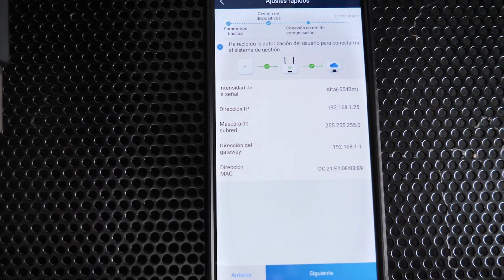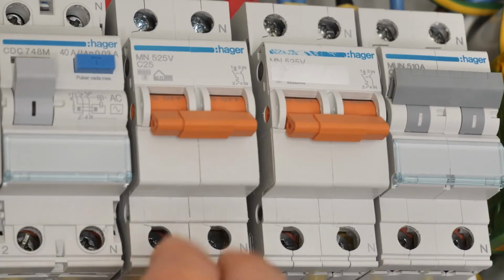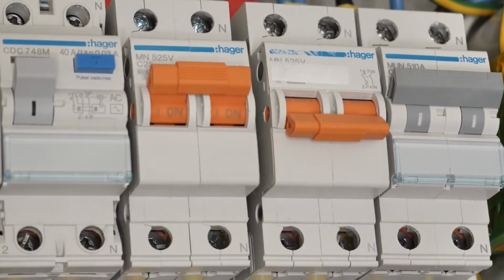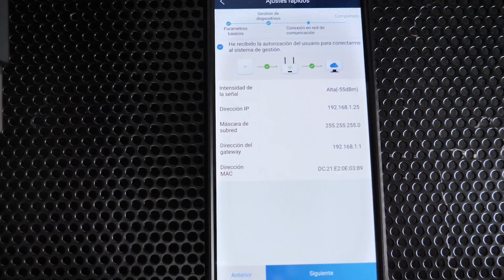In this case we could put the inverter into operation, specifically the alternating current part, since the inverter has already been configured. We would simply have to raise the alternating current protections so that the inverter receives power from the grid. It is going to synchronize, and from here it is already going to start injecting and could already work.